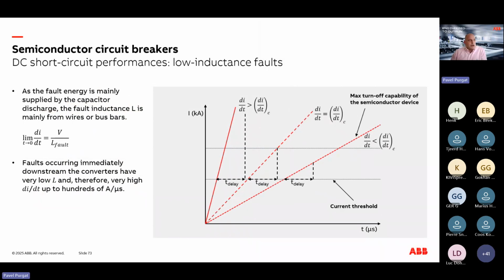One of the limitations of every semiconductor circuit breaker is the sensitivity to the system inductance, or to the di/dt, so the rate of rise of current. Now, as I said, we need to be sure that we are switching on a short circuit current. So we introduce a certain time in the circuit breaker to make sure that we have a short circuit.